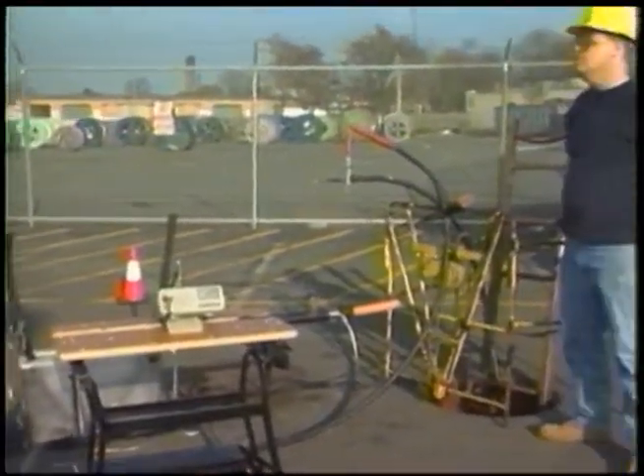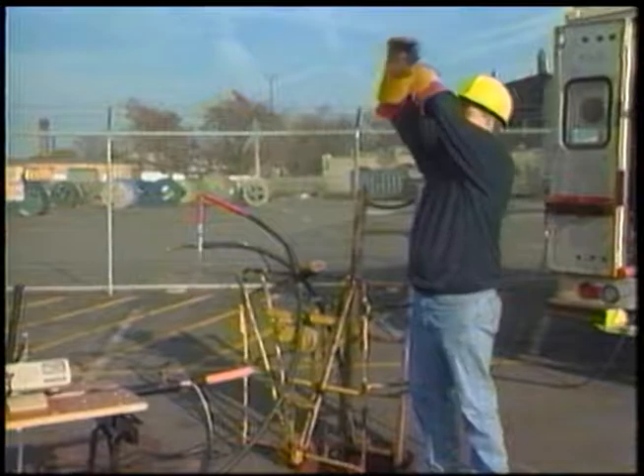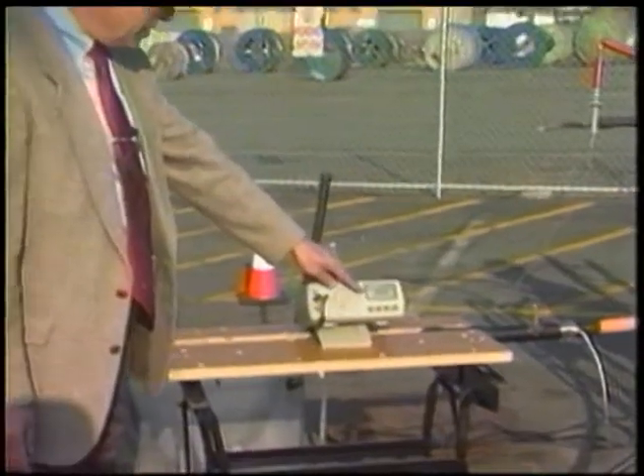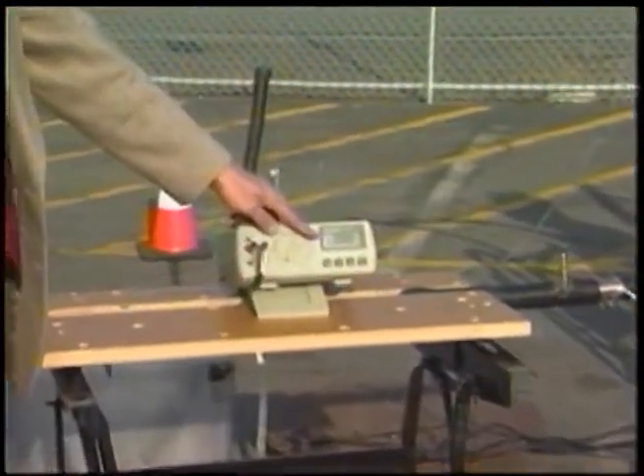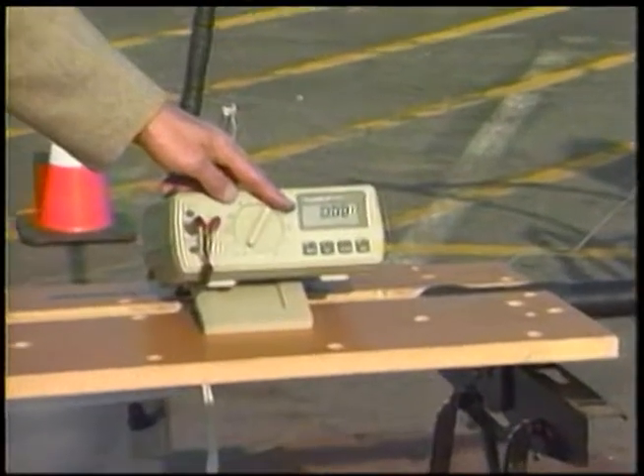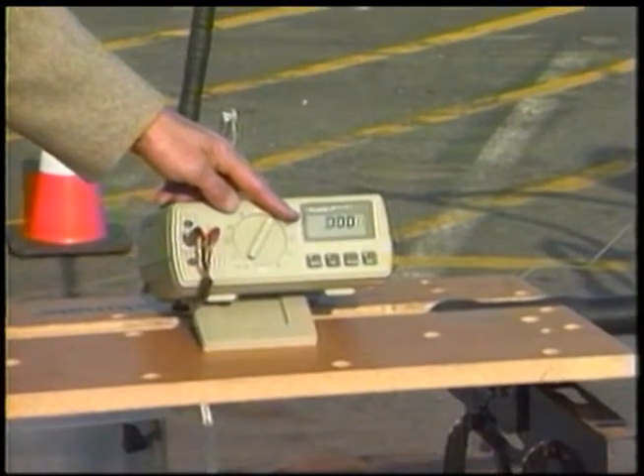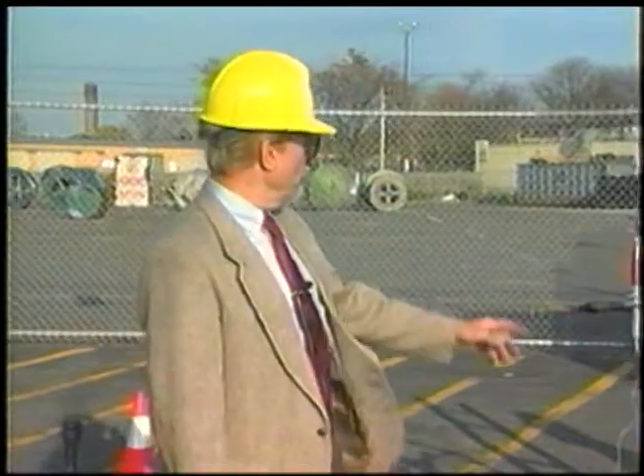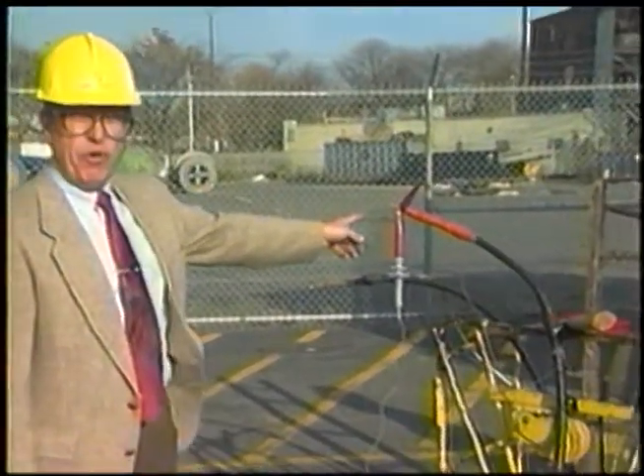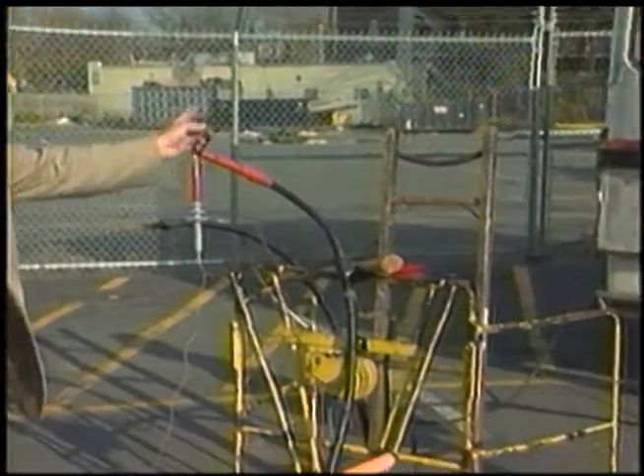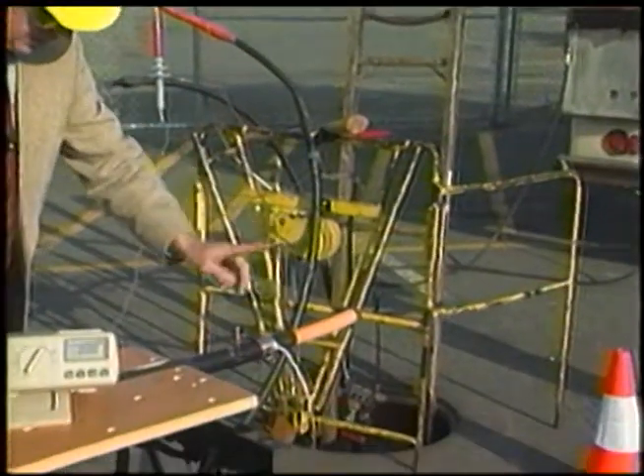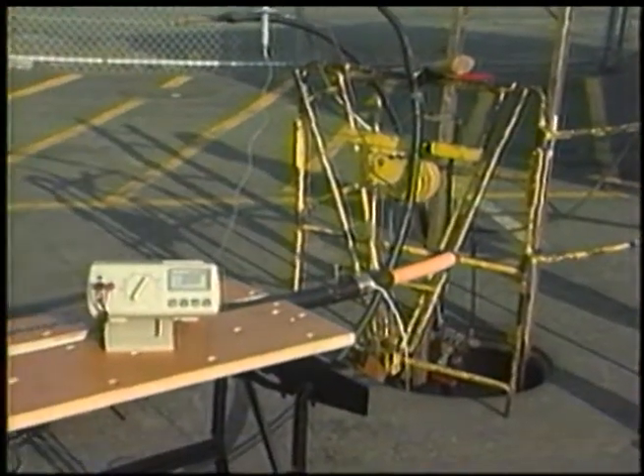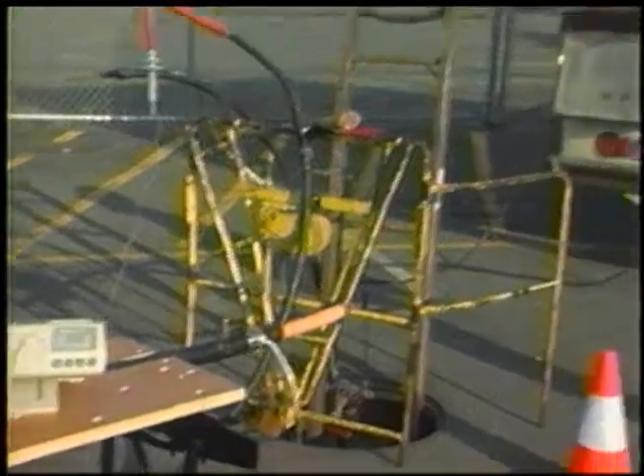Dennis, kill the generator. Now as we look at the meter, it says 0.000, which means the generator has shut off the transformer and now the cable is dead. Now that we showed you that we have 7,930 volts on the conductor, we're going to take that voltage and put it into this cable that has a fault. Okay, Dennis, energize the cable.